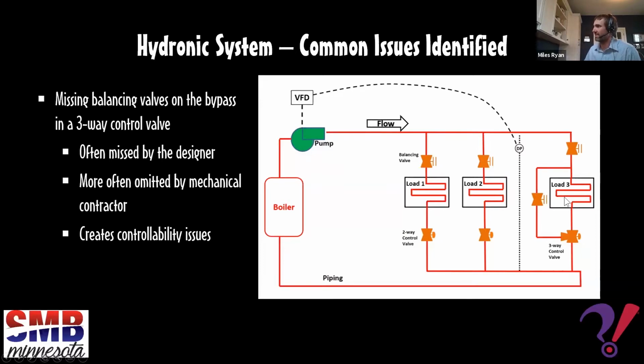Now, if it was a constant speed system where they had three-way control valves on every coil, then yes, you would match the pressure drop across the balancing valve to the pressure drop across the coil. However, in this scenario, on a variable speed system, when you have just one or a couple of three-way control valves, you're going to want to adjust this one. You're going to want to basically close all of the control valves to the loads and adjust that one to make sure that you're meeting your minimum flow requirements, whether that's for your steam converter or your boiler or whatever would be the limiting factor at the lowest differential pressure set point that you could realize.